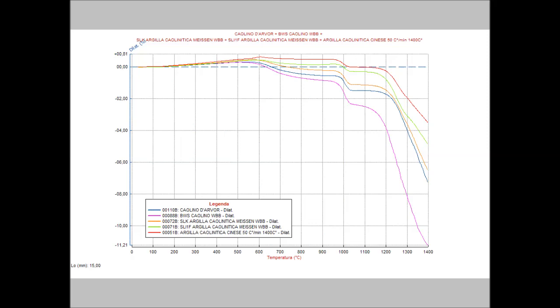One of the favorite fields of application of the optical dilatometer Misura HT is the control of the thermal behavior of ceramic raw materials. This is a comparison between several kaolinitic clays carried out with the heating rate of 50 degrees per minute up to 1400 degrees centigrade. Zooming the upper part of the graph, it is possible to have a better evaluation of the differences between the materials. Zooming only the part of the curve with the little fraction of the shrinkage, we can get a result very similar to the one of a traditional electronic dilatometer.